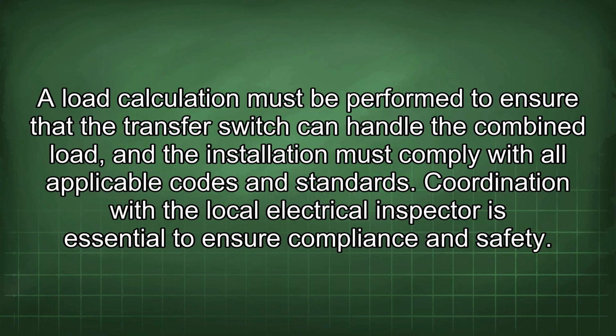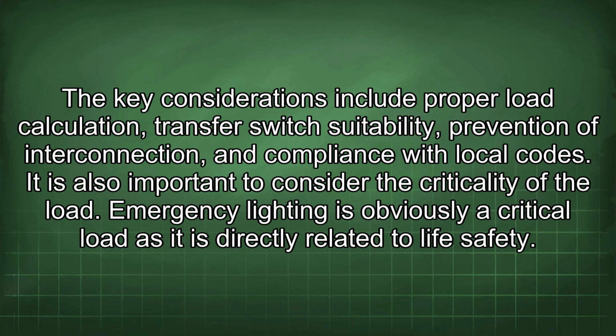A load calculation must be performed to ensure that the transfer switch can handle the combined load, and the installation must comply with all applicable codes and standards. Coordination with the local electrical inspector is essential to ensure compliance and safety. The key considerations include proper load calculation, transfer switch suitability, prevention of interconnection, and compliance with local codes. It is also important to consider the criticality of the load.